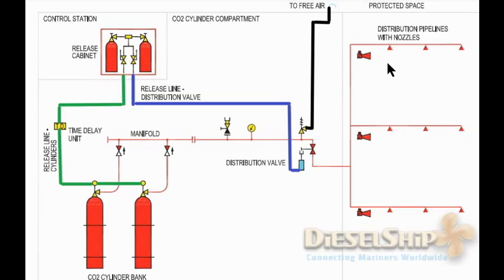In order to flood CO2 inside the engine room, the master mustering should be done first — a headcount order from the master. Then, with all confirmations with respect to your company policy, the master will give orders to the chief engineer to release the CO2. It is the chief engineer who has to release the CO2 into the engine room. Let's see what components are inside the valve control station.